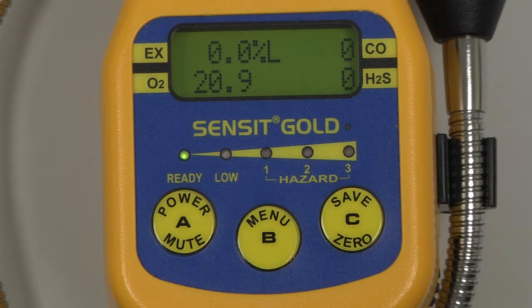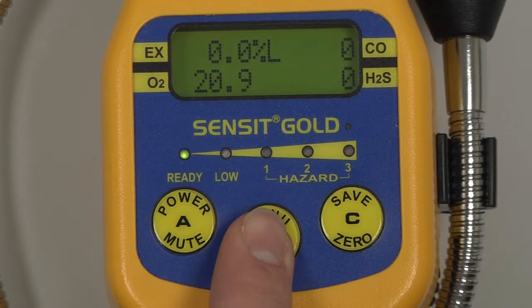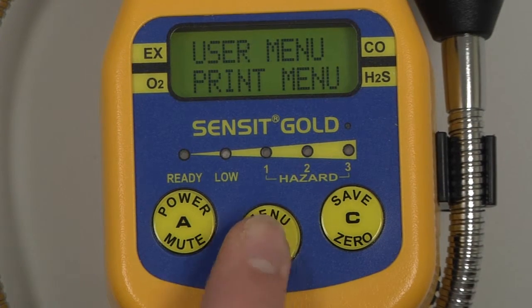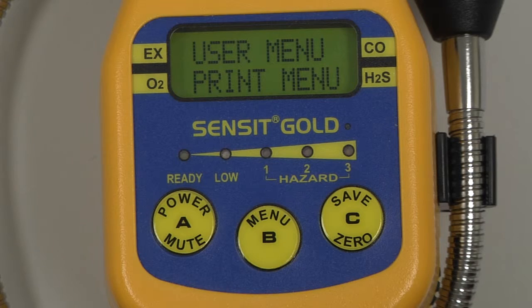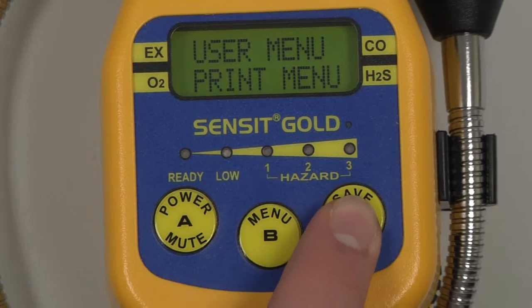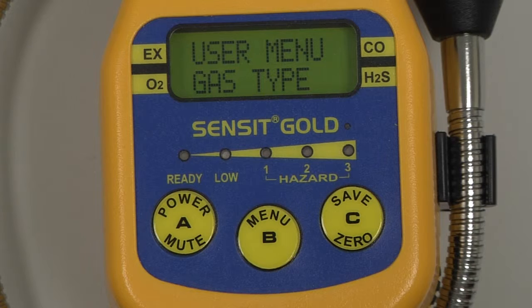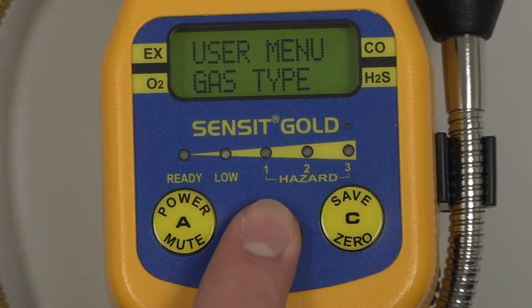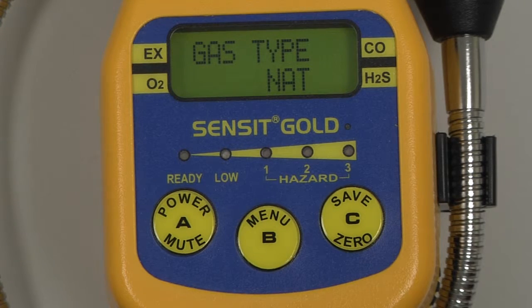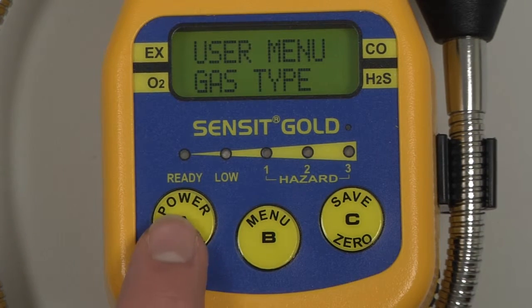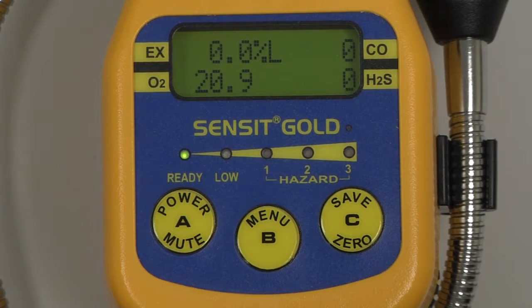To automatically calibrate for propane, we need to change the gas type in the user menu. To access the menu, press and hold the B button, and scroll through the menu by pressing and releasing the C button until gas type appears. Select by pressing and releasing the B button, and if natural gas is selected on the screen, we can select propane by pressing and releasing the B button, and saving by pressing and releasing the A button, and again to return to the work display.